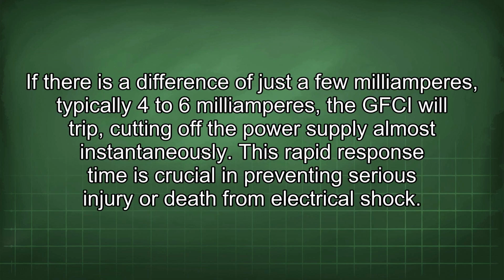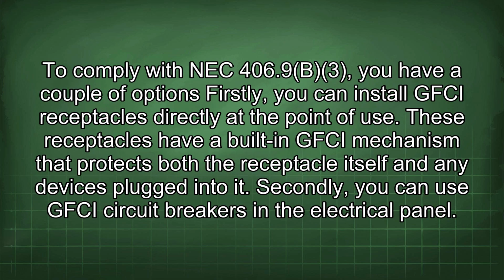If there is a difference of just a few milliamperes, typically 4 to 6 milliamperes, the GFCI will trip, cutting off the power supply almost instantaneously. This rapid response time is crucial in preventing serious injury or death from electrical shock. To comply with NEC 406.9(B)(3), you have a couple of options.